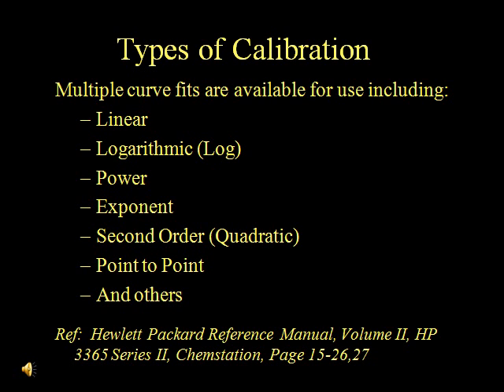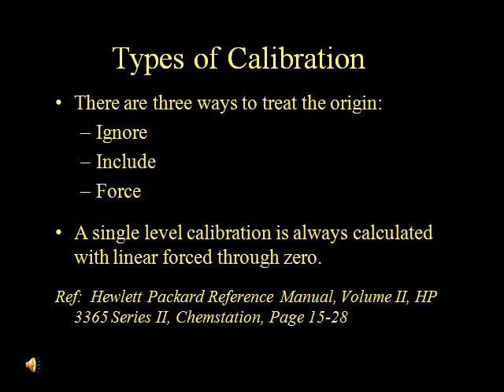There are many types of calibration curve fits that are available for the analyst to use. Some of the curve fits include linear, log, power, exponent, quadratic, point-to-point, and other less commonly used curve types. An important consideration in selecting a type of calibration is the treatment of the origin. There are three ways to treat the origin: ignore, include, or force. A single level or one-point curve calibration is always calculated with linear force through zero.